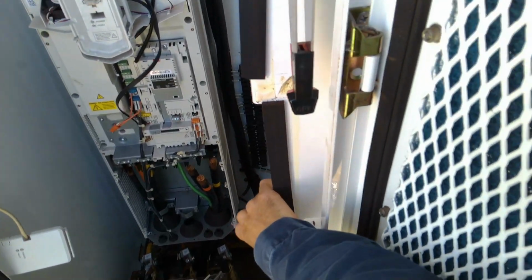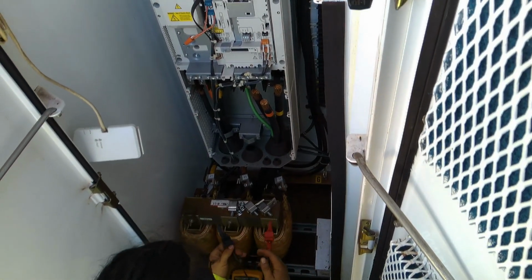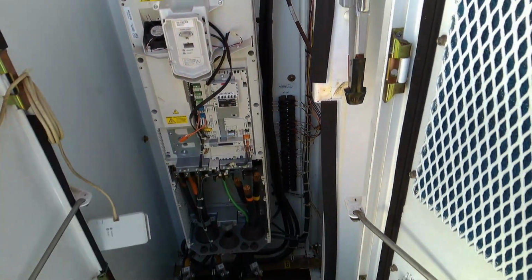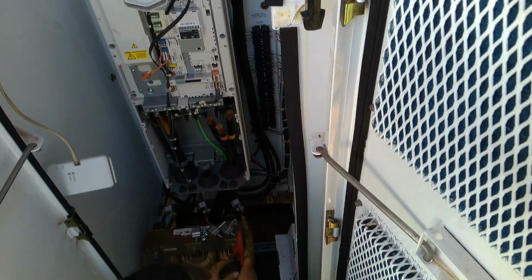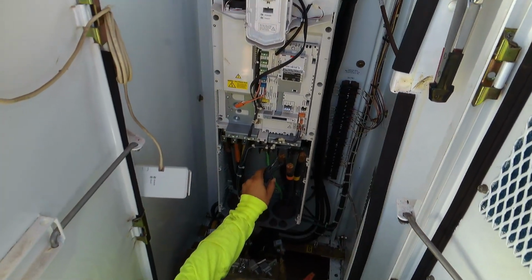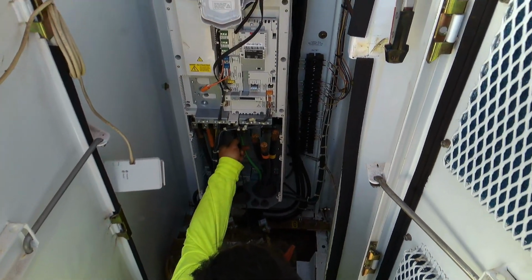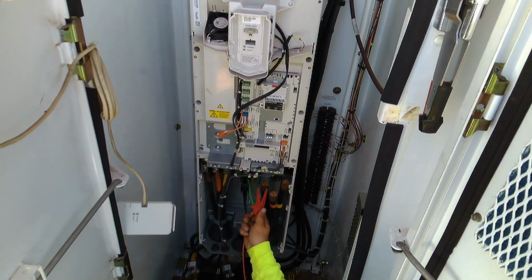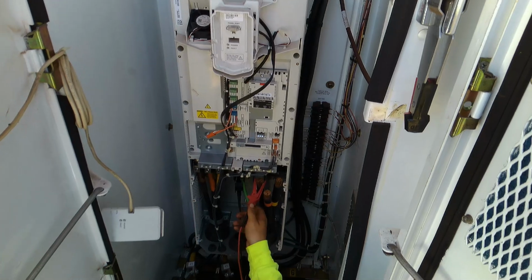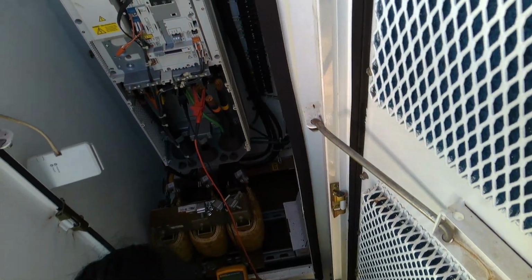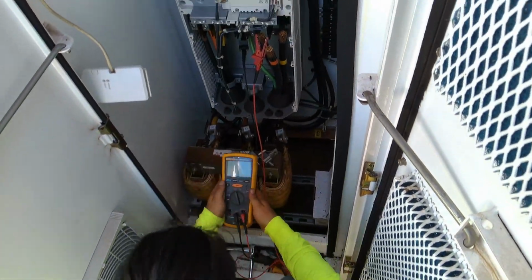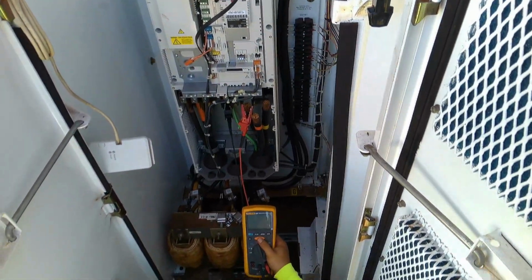Exact same thing we did down in the hole. Go ahead and put your red lead onto insulation. Then you're going to put your black on a good ground reference. Nope. That's a good ground reference. Then you're going to clip onto him. Very good. And then you're going to put it on 1,000 volts. And you're going to lift that thing up so I can see the reading really good. Yep, there you go. Now hold down test.